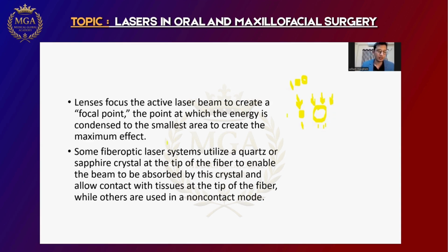Now, some fiber optic laser systems utilize a quartz or sapphire crystal at the tip of the fiber to enable the beam to be absorbed by this crystal and allow contact with the tissue at the tip of the fiber, while others are used in non-contact mode. Now, this crystal, the quartz or sapphire crystal, absorbs the laser beam and heats itself, and this heat results in thermal cautery.